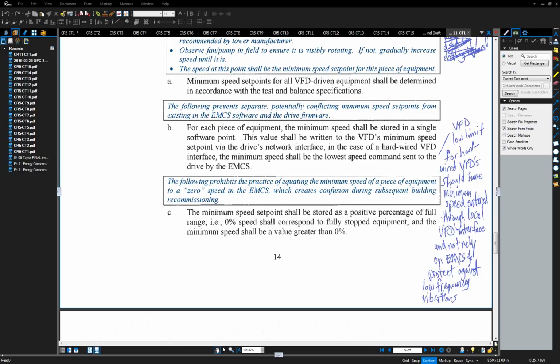So I guess we would consider it, whoever sets up the variable speed drive should be setting up finding frequencies and so forth where it might be unstable and making sure that it can't operate under any unstable areas. Well, we're talking about minimum speed here. We're not talking about stability in operation across the range. So if you're worried about blanking out a harmonic frequency, something that would cause vibrations on a fan or a pump at a very specific speed, that's a completely different issue, and it's not even addressed in this document. All we're talking about is minimum speed. So that's fine. You don't have to do anything with that comment then.